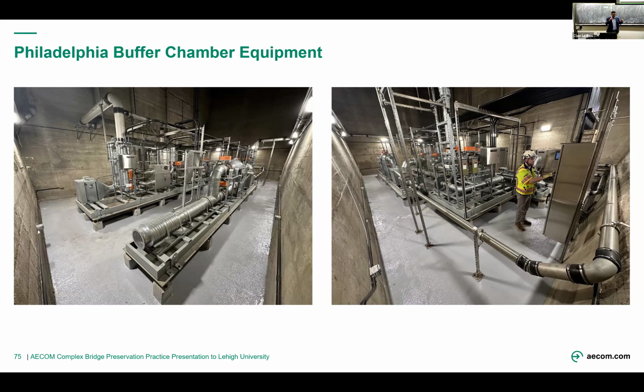There are valves used to balance everything. It's like a pipe organ, and it was very difficult to balance, because this also supplies air into the anchorage chambers on the opposite side of the river. The air dumps out the end, so you have to create back pressure and adjust each valve as you go. You get a lot of pressure in the beginning that really drops off, so you have to close the valves closest in to push the air further.